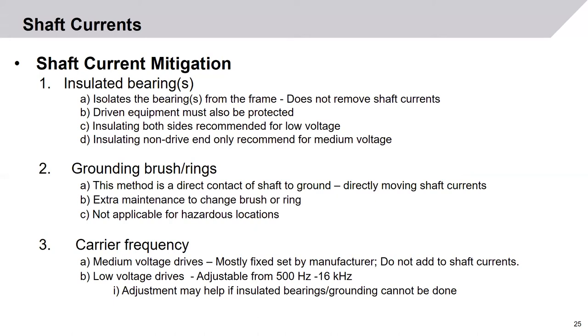A second method is utilizing ground brushes or rings — a carbon brush or a ring of carbon fiber that makes direct contact with the shaft to ground, directly moving shaft currents. However, this method requires extra maintenance to change and/or clean the brushes or rings. As this is an arcing device, it is not applicable for hazardous locations.